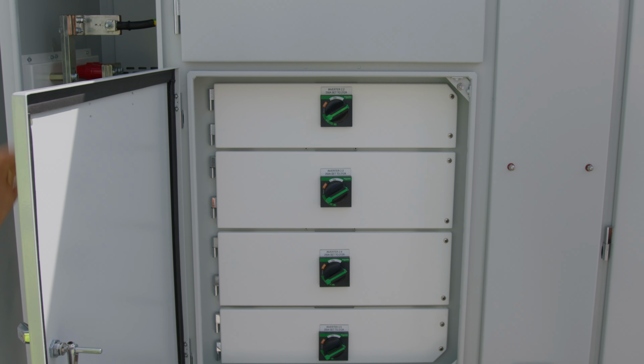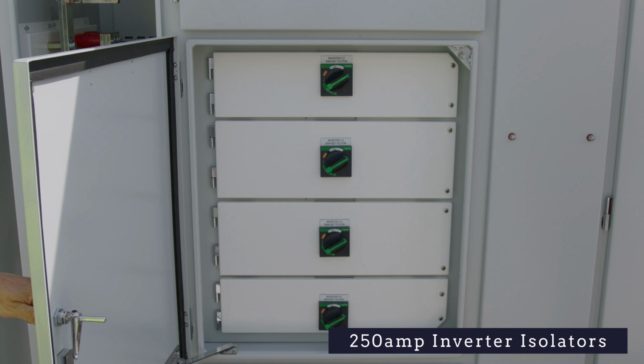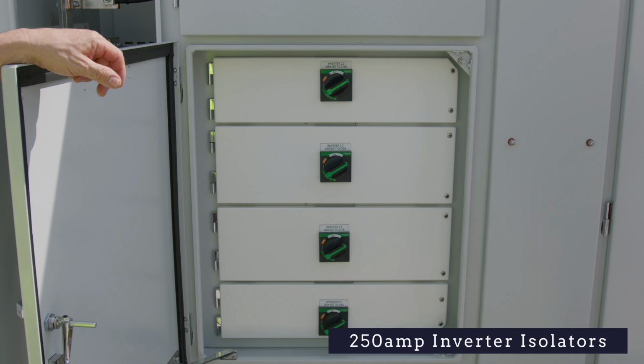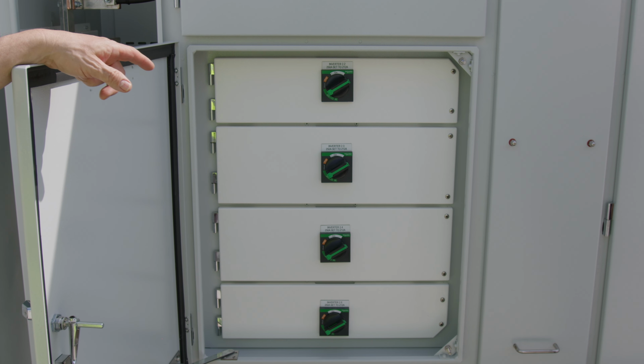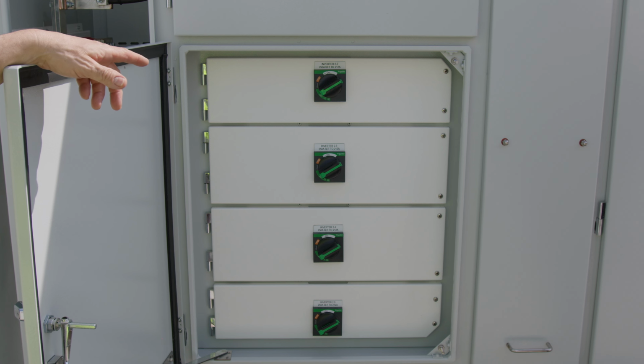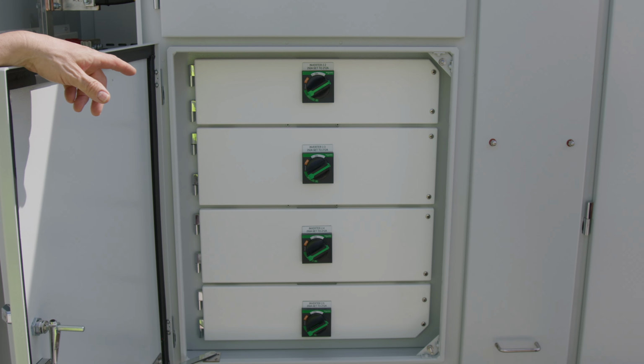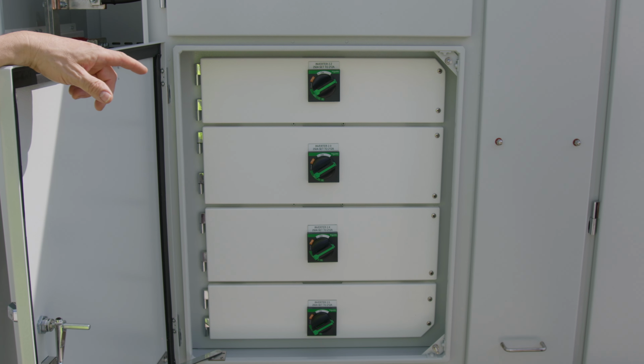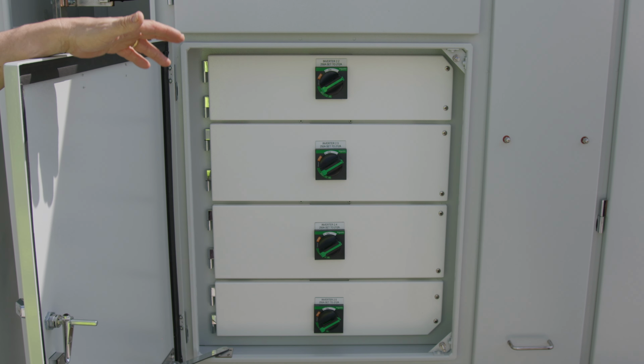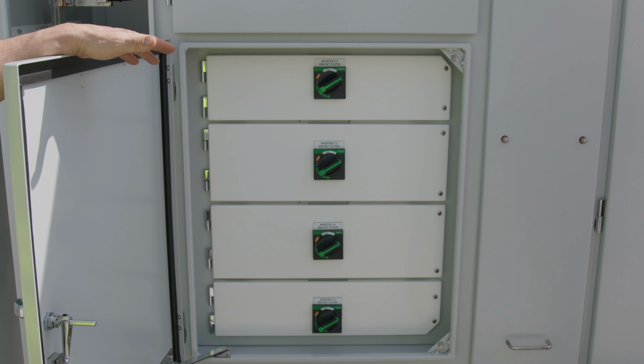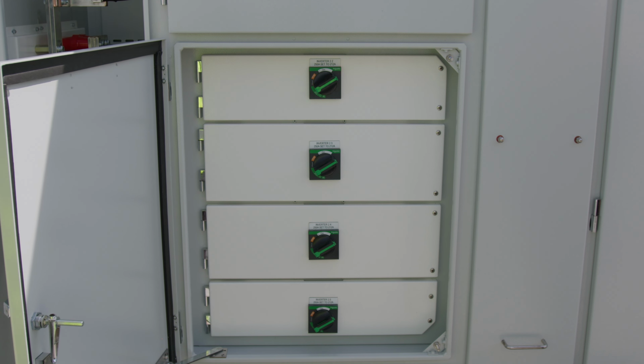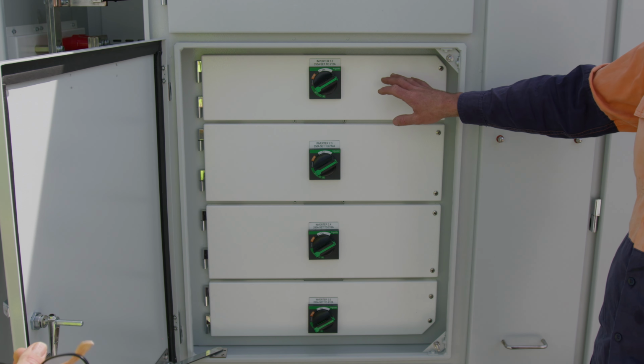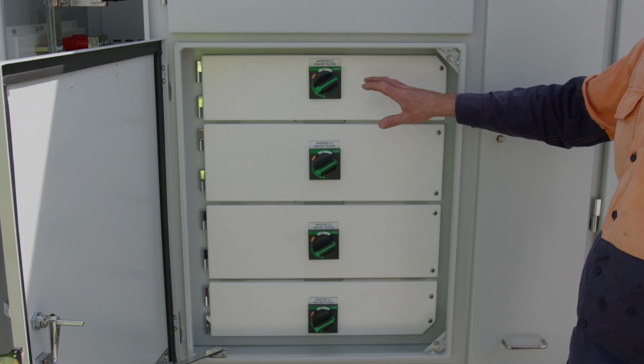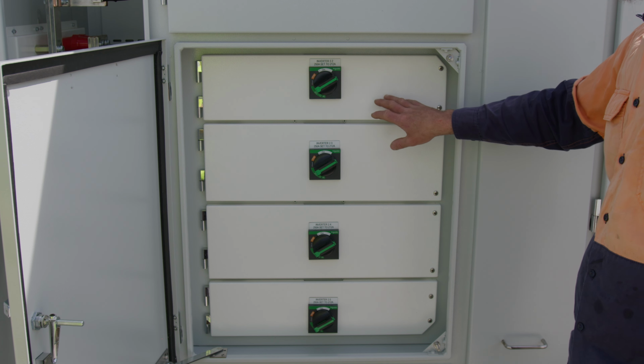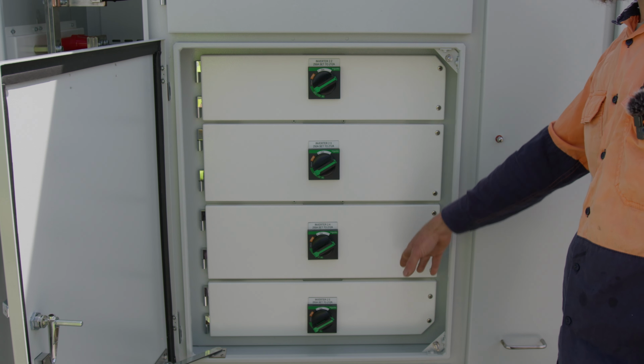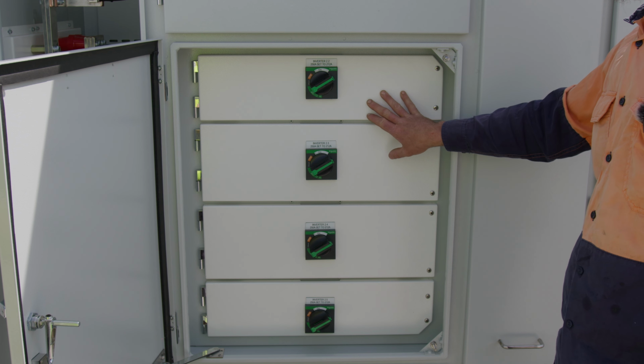So here we've got this cabinet, this section, it's inverter isolators with some numbering. So we've got 250 amp isolators, and they're set to 212. So this is a circuit breaker, isn't it, here? Yes, this is a circuit breaker. This is the circuit protection for the cabling. So inside the inverters we have isolators, with no circuit protection. The circuit protection is offered here at the main board by these circuit breakers.